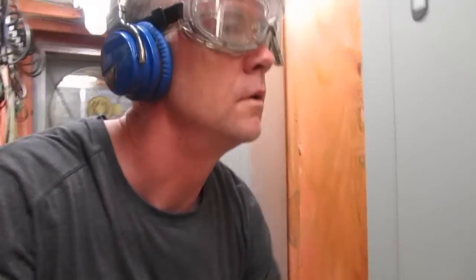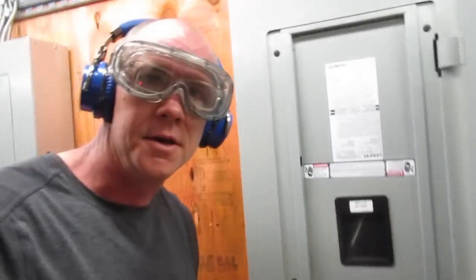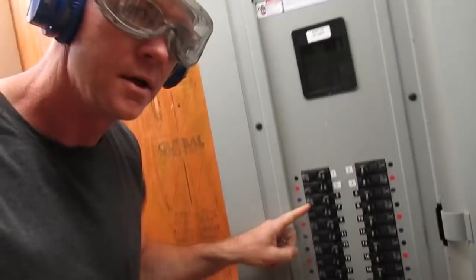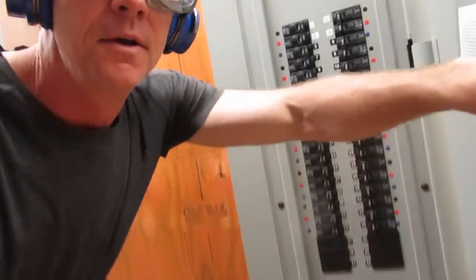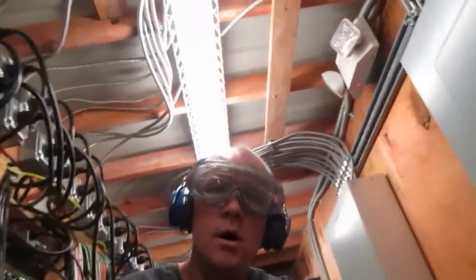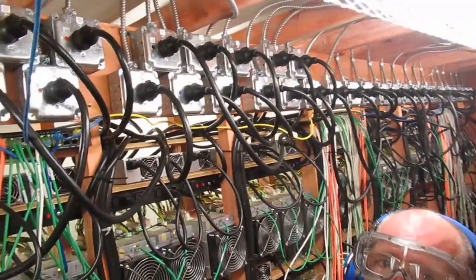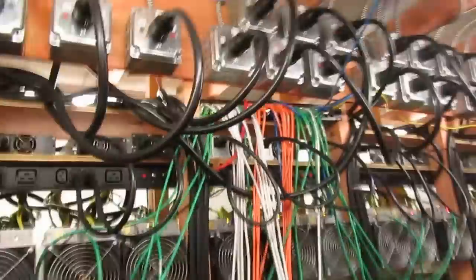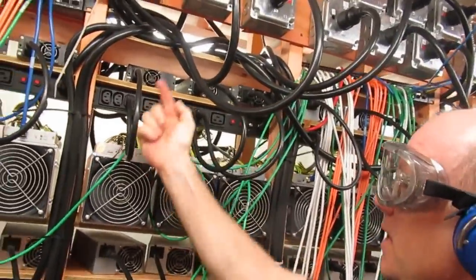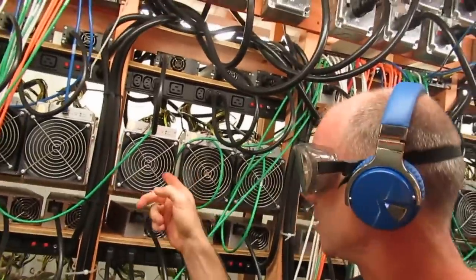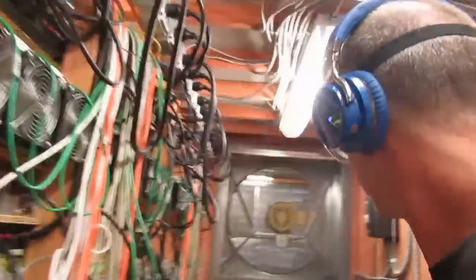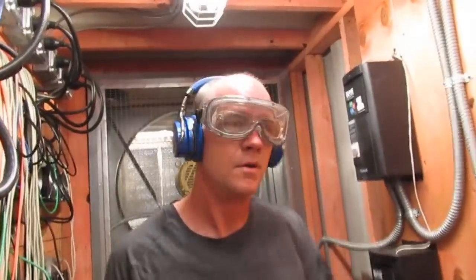PDUs, power distribution units. So I'm going to show you inside the panel here, and you can see these are all 30 amp connections. And if a breaker trips by chance, we can reset it. And we also have some room for expansion. We've got about 50 overall outlets here, which supplies about 210 miners overall. And each of these is about a 5,000 watt outlet. I figure next one I could probably do about 300 miners. There's a little excess space in these shelves, and I could probably get 70 to 75 outlets.